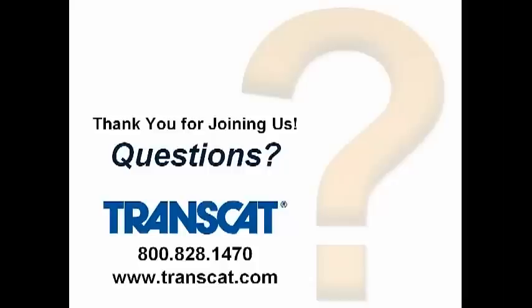Another question is, how can Transcat, I think it's judge in-out tolerances without uncertainty? All of our calibrations are accredited. We have uncertainties for every one of those readings, whether we report them or not. And we actually have a new tool that we've developed and have put into place so that our technicians can see when they're performing the calibration. That is called the Probability of Compliance to Specification, or PCS tool. That allows them to understand where they are relative to the tolerance limits and our uncertainties. So that information is being used and is available at all times, whether the client receives that information or not.